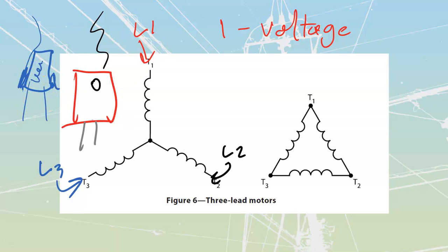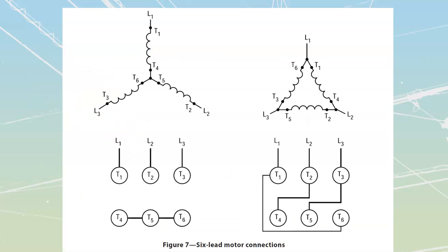I don't know whether you're a journeyman or as strict on it as I was with my guys, but I did not abide having upside down marrettes, particularly in places where the stuff could be washed or it could be exposed to weather or anything like that. Condensation even, running in. If you've got a hot area and a cooled area, hot is going to be inside of a motor, cold is going to be outside. That condensation can run down inside there and corrode it. So just caps up, guys. Caps up all the time.